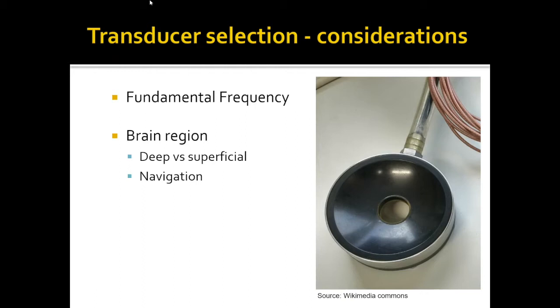Your outcome measure will also influence the type of transducer you want. For example, if you want to study online effects with TMS, transcranial magnetic stimulation, you should probably look for something very slim and non-ferromagnetic, with no steel in the transducer. Similarly, if you're looking at fMRI studies using the transducer in the MRI room, you should also keep ferromagnetism in mind.